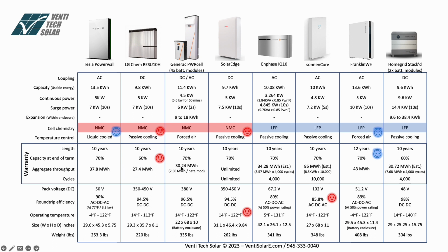The number here is calculated based on how many battery modules. They're expecting 7.56 megawatt hours per battery module. Since we have 4 battery modules, we get to 30.24 megawatt hours at the end of 10 years at 70% of battery life. Now, SolarEdge says that it's unlimited on the number of cycles and unlimited aggregate throughput. We're going to leave that for a moment and come back to it. Let's keep on analyzing the rest of the vendors.